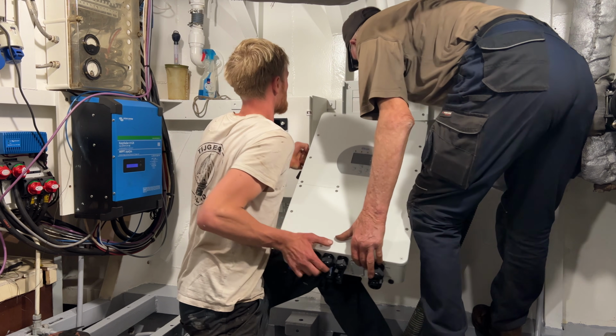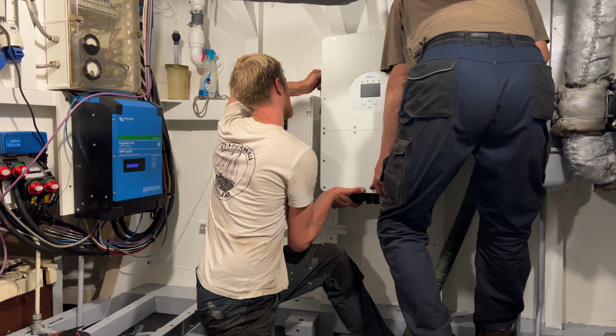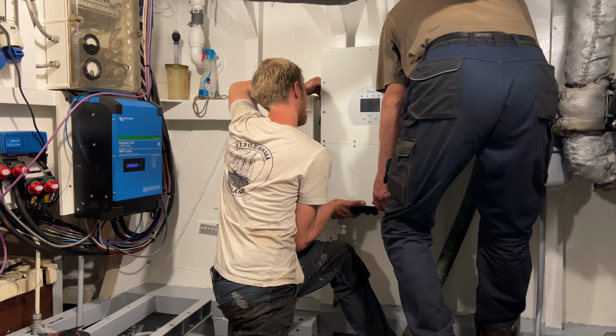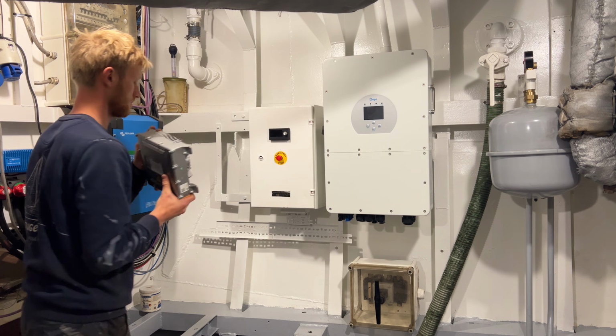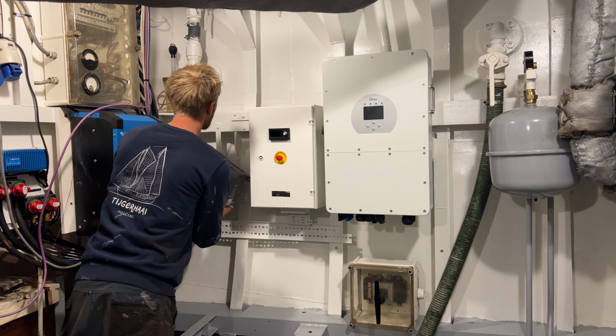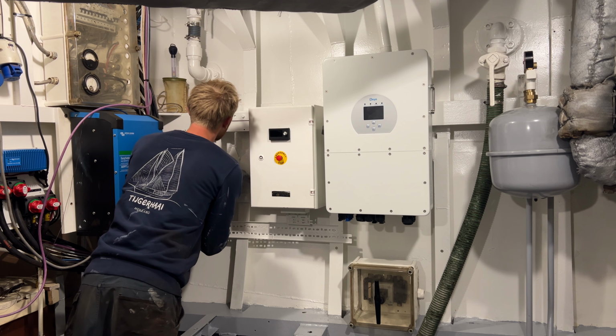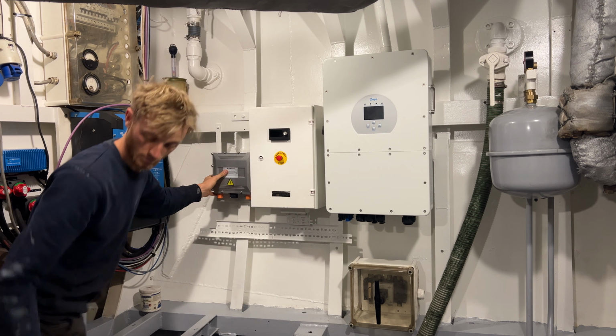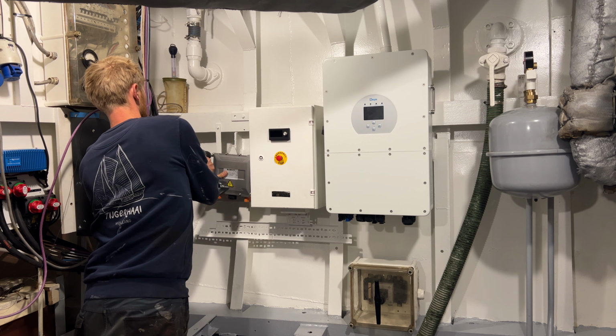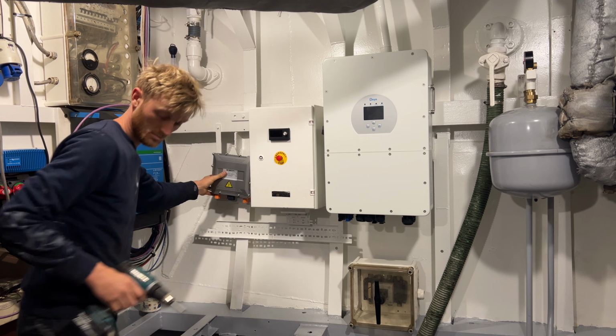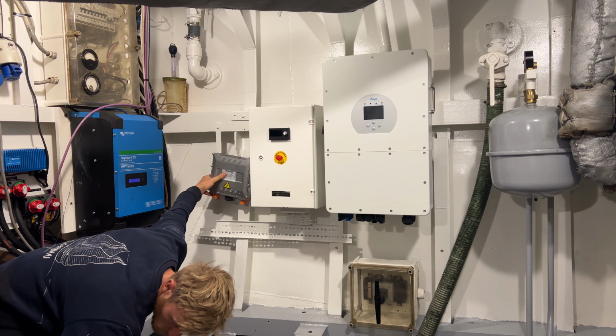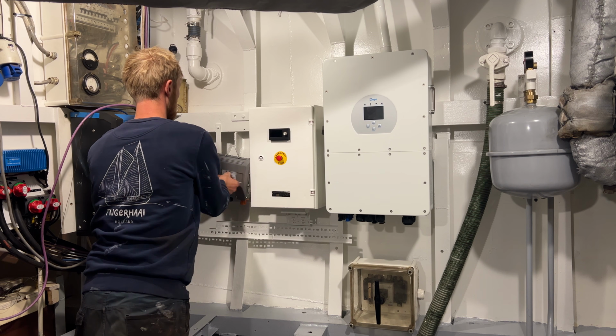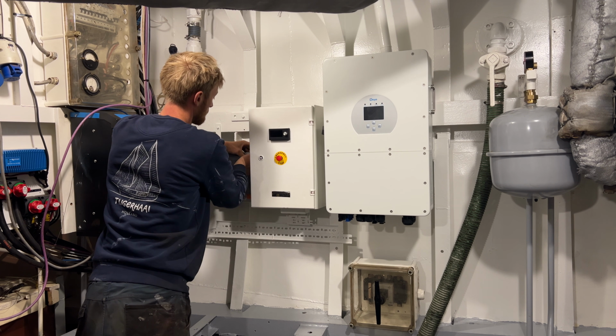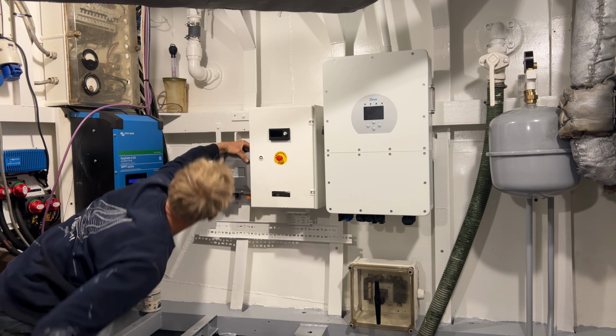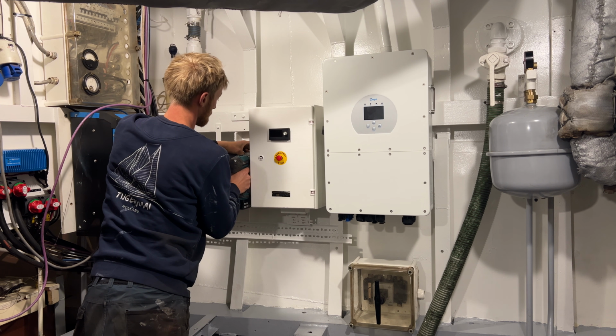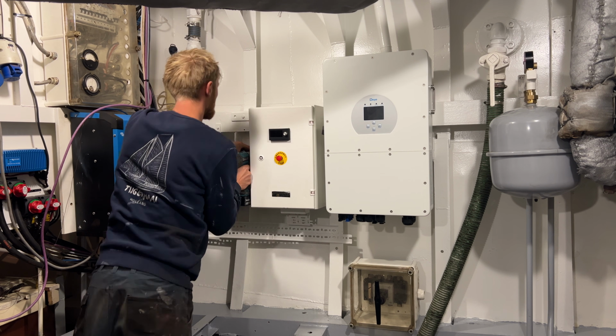Both chargers are programmed with a safety margin on the batteries. We're never charging them all the way to 100%, but more like 85 to 90%. And the inverter won't pull them lower than about 10 to 15%. That means the cells are never stressed to the extremes, which reduces the chance of failures and significantly increases the lifetime of the batteries. It is important to mention that these are not fast chargers. The big one is 20 kilowatts, which can charge the whole pack in just over 3 hours, but that is nothing compared to fast chargers for electric cars along the highway, where going from 10 to 80% typically takes around half an hour.